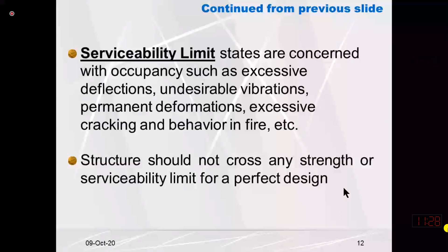A structure should not cross any strength or serviceability limit for a perfect design. So who puts this limit? This limit can be taken from the code or design specification, or if you are an experienced engineer or designer, you can put your own limit based upon your design. For example, I do not want the elastic deformation of the first floor of a hospital building to be more than 10 millimeters. Why? Because on the first floor we might have installed an X-ray machine or a laser machine. If the deflection is excessive, the alignment of the laser machine or X-ray will be disturbed. So we want to control the serviceability.